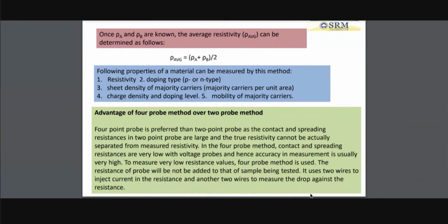See, the resistance of the probe will not be added to that of the sample being tested, and it also uses only two wire pairs. Totally you get only four wires. So two wires go to the current side and two wires go to the voltage side. That's all, very simple. They inject the current through the resistance, and the other two wires you use to measure the potential difference. So in that also we reduce the error.